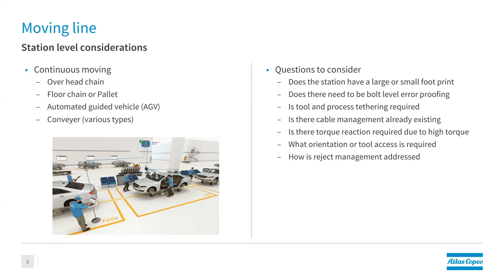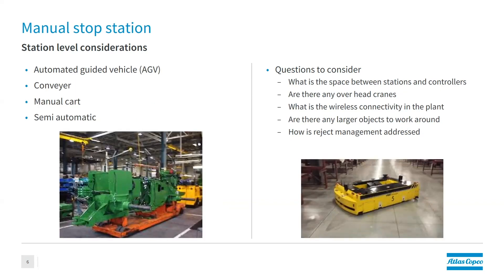Is torque reaction required due to high torque? On a moving line you'll generally have lower torques, especially in final assembly, but in powertrain you may have high torque, so we have to think about torque tubes or torque arms. Orientation matters too — you sometimes want those perpendicular to the line rather than parallel. Finally, consider reject management: if a part fails, does it split off to a repair bay, or does it complete the process and go offline at the end?